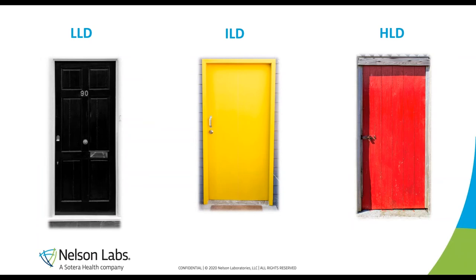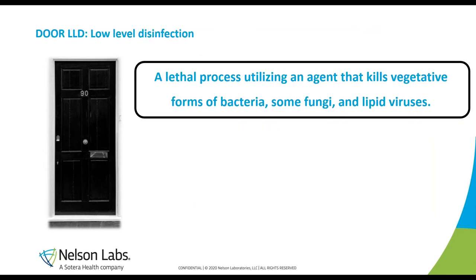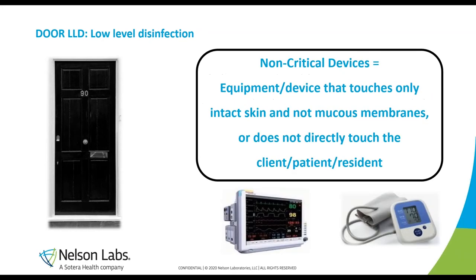When you start the road trip for your disinfection validation, you can choose three doors: black, yellow, or red — each representing a specific level of disinfection. The black door represents low-level disinfection, a lethal process that kills all forms of vegetative bacteria, some fungi, and some viruses. You can use this level when dealing with non-critical devices — those that do not directly come in contact with the patient, or only touch intact skin.